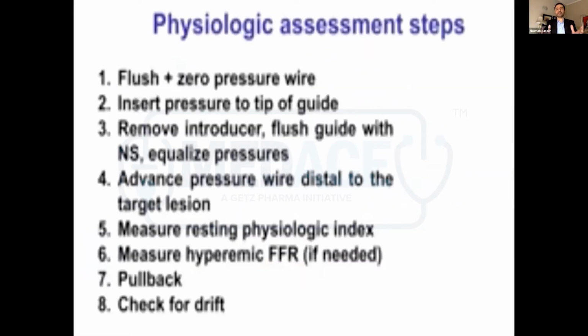So what are the steps you need to watch out for? This is some of the FFR wire. Once you take the wire out, you need to flush. Then you need to calibrate or press the 0. Most of the time with the Volcano wire, when you connect, it's an automated 0 system. Insert the pressure wire to the tip of the guide, and then remove the introducer. That's very important, to remove the introducer for the wire, and flush the guide catheter with normal saline, and then push the equalize button to equalize the pressures.